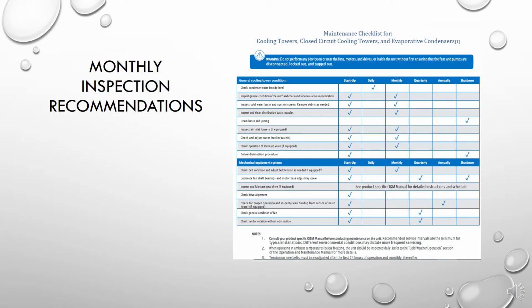And because we felt like everyone needed one more document for reference, we created a checklist or inspection procedure for the cooling towers here on campus. What that looks like is just some recommendations on how frequently we need to check these different general cooling tower condition items. If you don't know, this is a good resource for you to use to figure out what you should be doing at startup, daily, monthly, and at shutdown. It's not an exhaustive list, but it was compiled based on the recommendations of all of the cooling tower manufacturers.